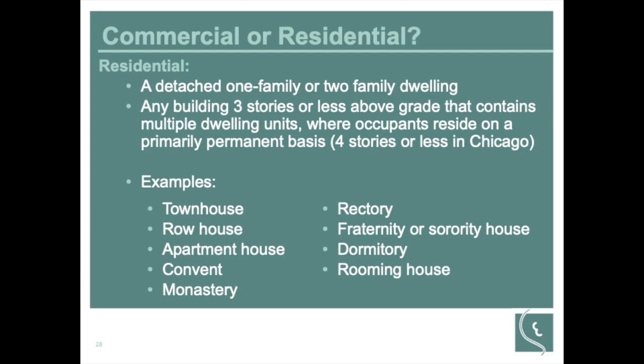The definition of a residential facility within the code is a detached one-family or two-family dwelling or any building 3 stories or less. In Chicago, it's 4 stories or less. That it's used primarily for permanent occupancy. If you've got a mixed-use building where the ground floor has commercial and the upper 2 floors are residential, the ground floor section would have to meet commercial code within the individual spaces, but the envelope of the building, the residential section, would all meet residential code. That would be under the residential provisions because it's a primarily residential facility.